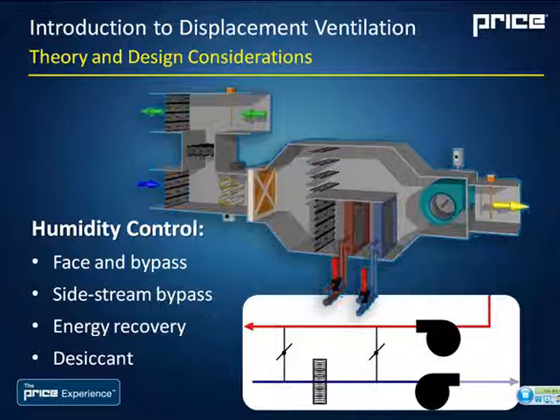Systems like a face and bypass or side stream bypass, where you can just bypass some of that warm return air, which is around 80 or 85 degrees up to 90 degrees, and mix that with your 55 degree off coil air and get your 65 degrees out. Other systems, in cases where you can't do return air mixing, so things like hospitals or labs, where it's got to be a straight shot through and out the room, energy recovery becomes very advantageous because you can take advantage of some of that sensible heat and reheat your supply air.